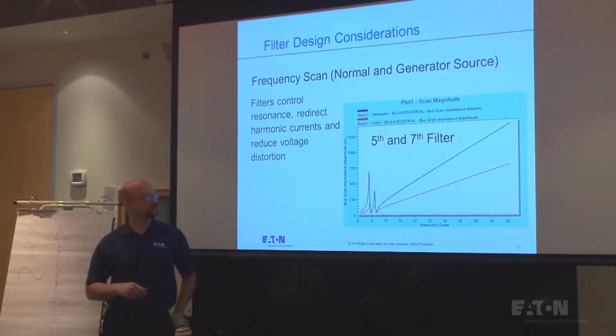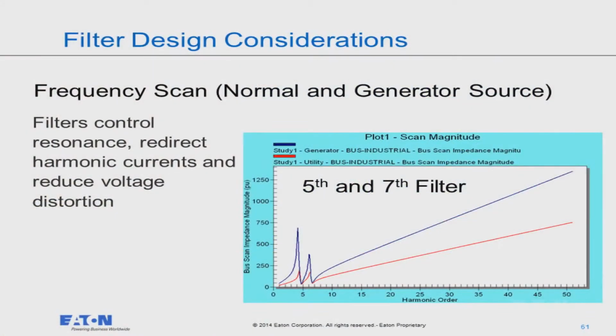Here's a multi-stage filter. If I was going to filter more than one harmonic, I'd do the fifth and the seventh, because those are the two predominant ones. Why would I not want to put just a seventh harmonic filter on? Does anybody know? The fifth would be the worst.